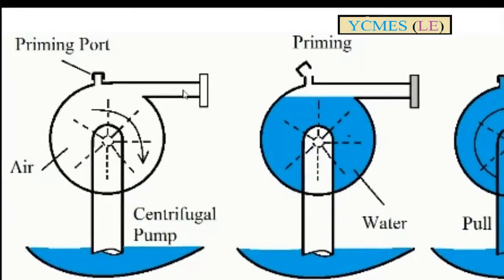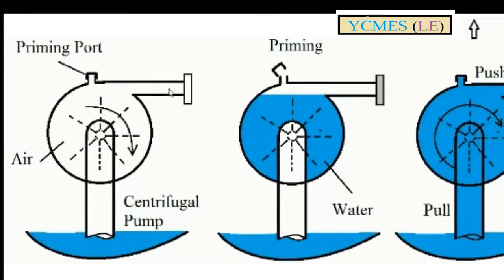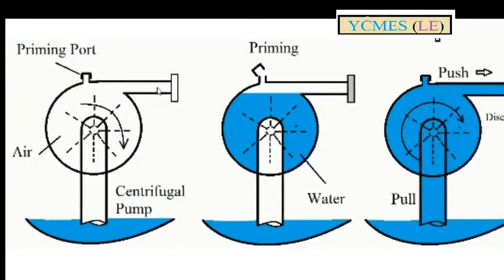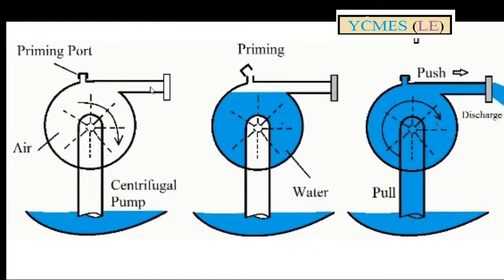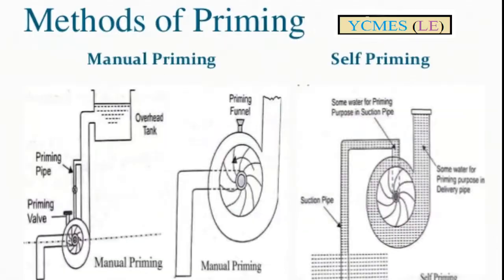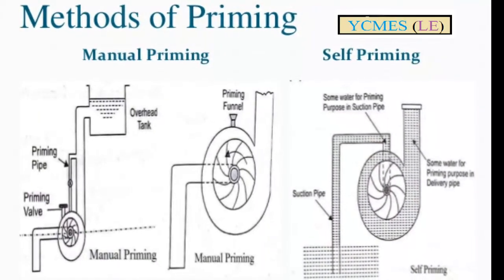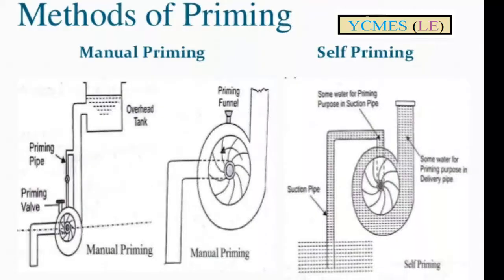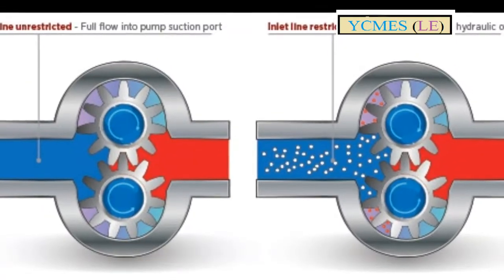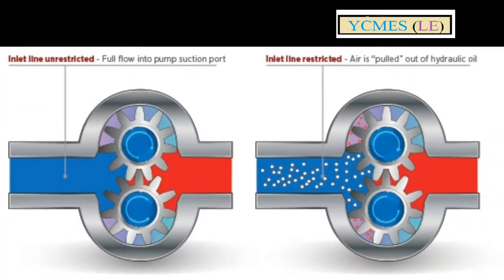When we start a new pump, we need to do priming first. The reason is that the casing and suction pipe may contain air. The air must be removed, and water must be poured into the pipeline so the pump can discharge water properly.